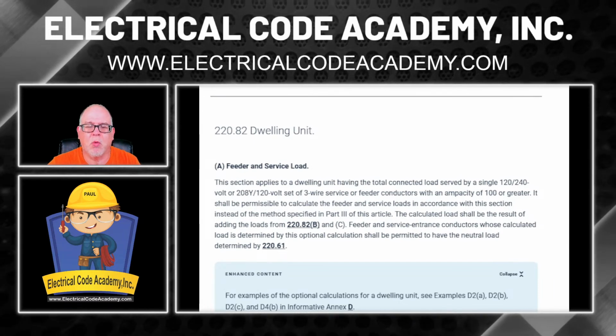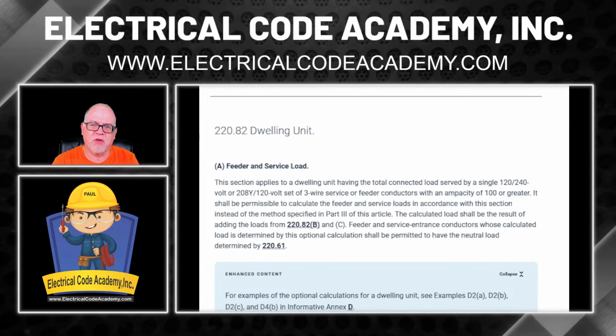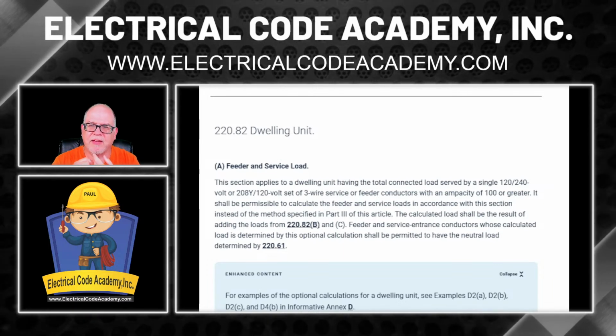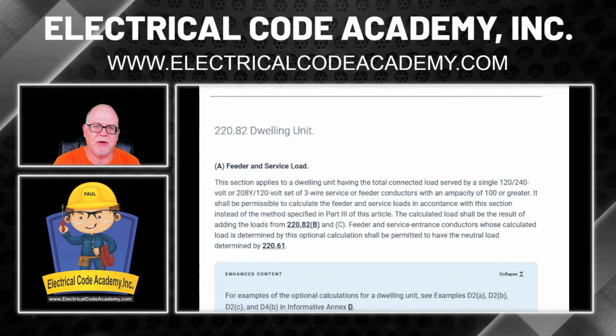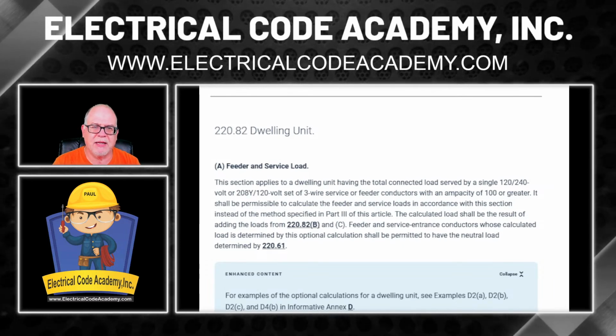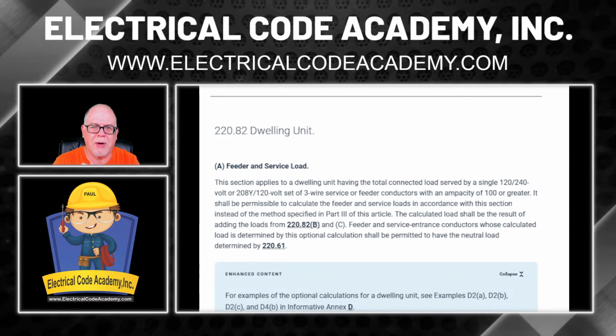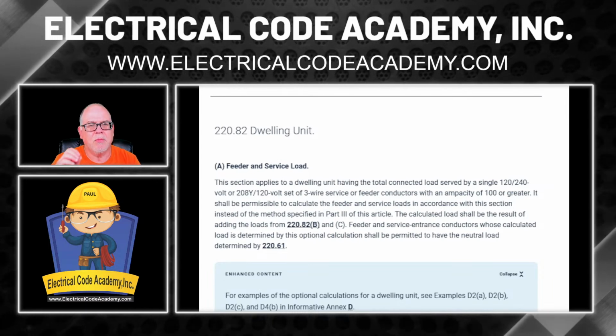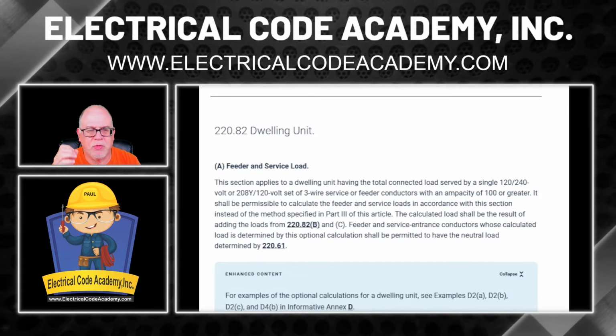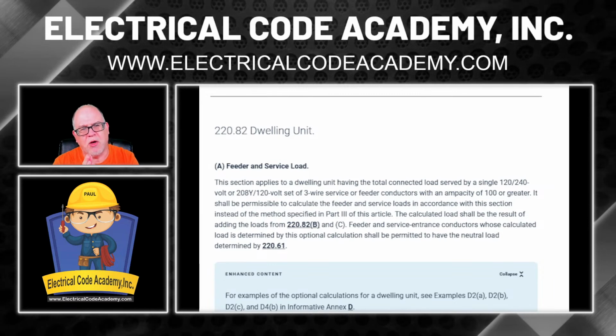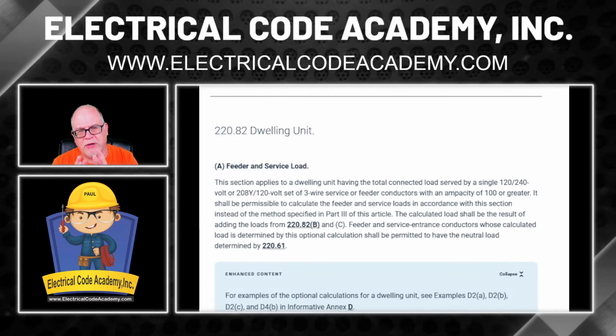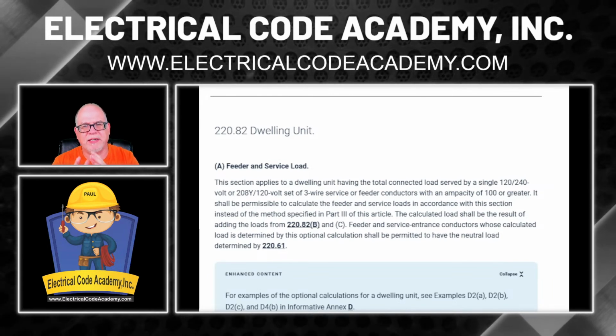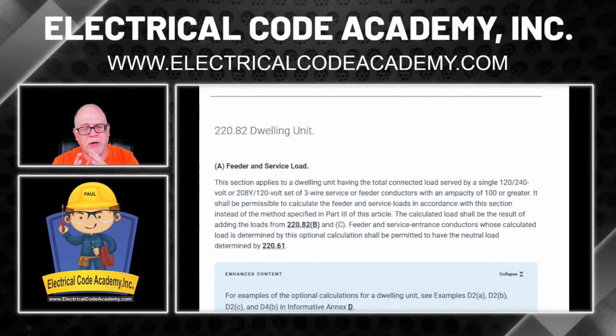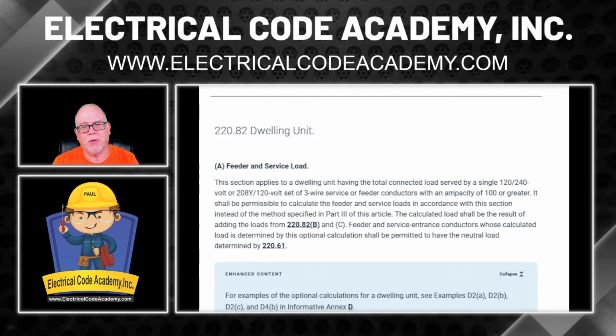What you see is it talks about feeder and service loads, and it tells us that since it's a dwelling unit, we're going to follow this optional method if it's a 120/240 or a 208Y/120. Even though it was 230 and 115, we know that the nominals are 120/240, so we're dealing with a single phase 120/240. But that's not the most important part here.